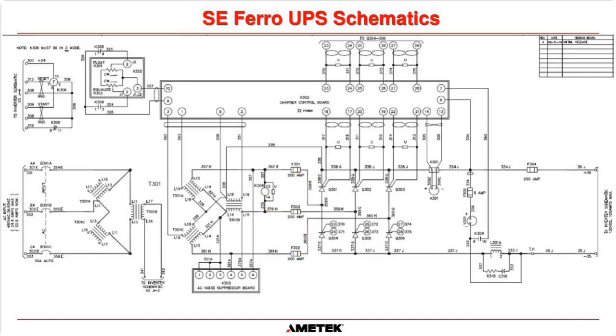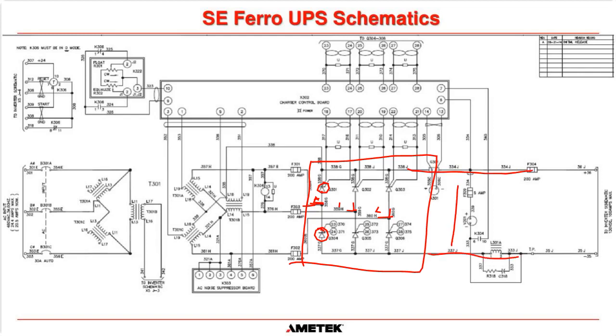Okay. So here's our rectifier bridge here, and it's actually quite simple. We have 3-phase going in the middle of each pair of SCRs. So this is an SCR, a silicon controlled rectifier. Okay. And you can see we're tied into the midpoint, the anode of this one and the cathode of this one, and the same for this one and this one here. So we have 3 phases, A phase, B phase, C phase going in and then out. If you measure across here, we have DC. So it really is as simple as that. We have AC going into the SCRs and DC coming out of the SCRs.